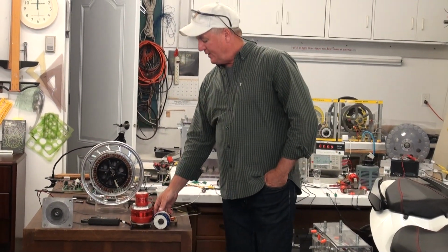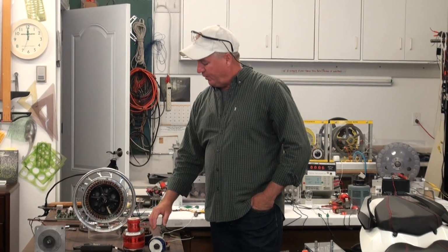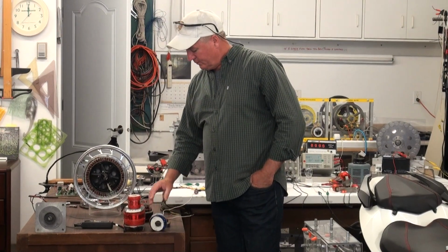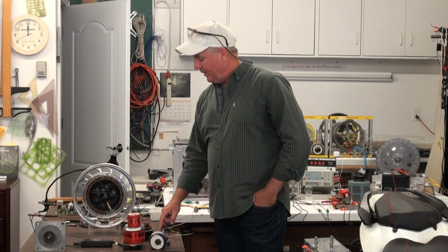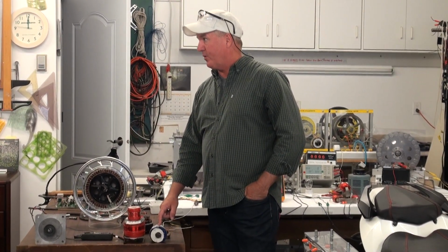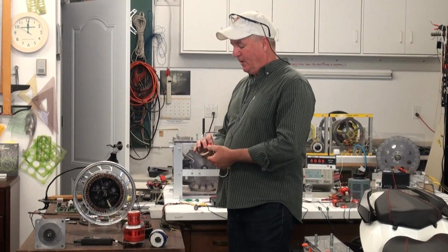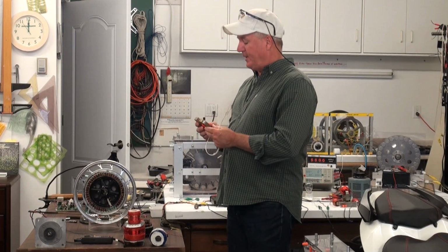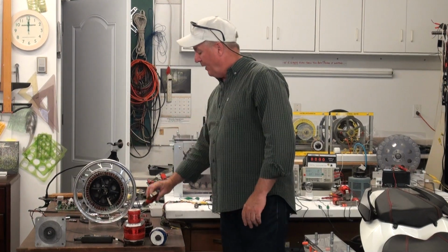In 2010, this two-coil approach was integrated into a single coil, and then the technology improved from 2010, where we were delivering about 1 amp per coil, to 2018, where we now have commercially manufactured coils that this coil will deliver between 10 and 20 amps of current.